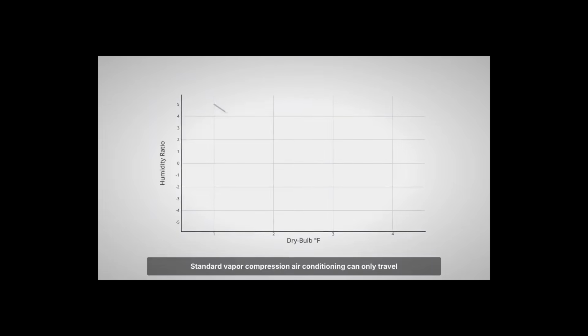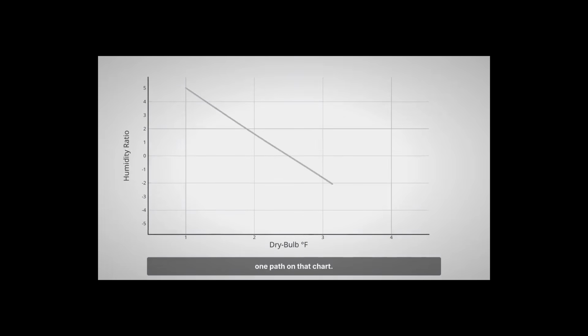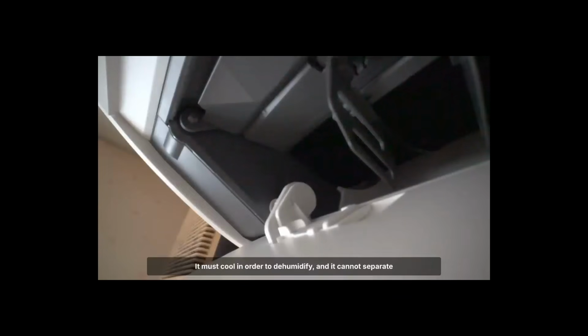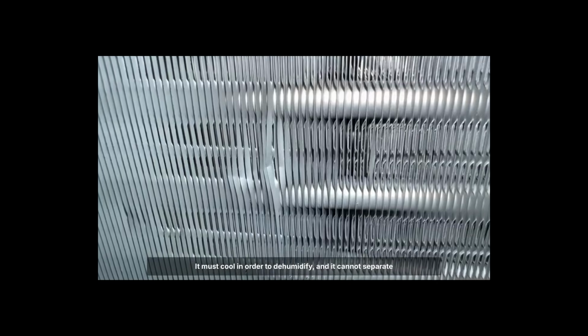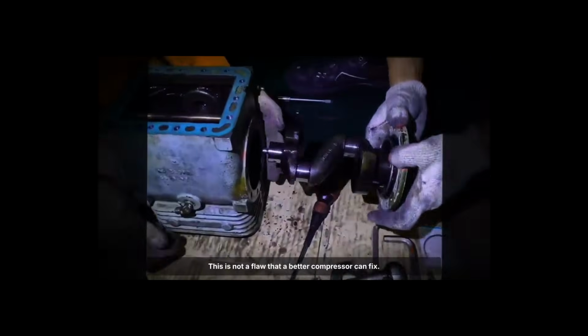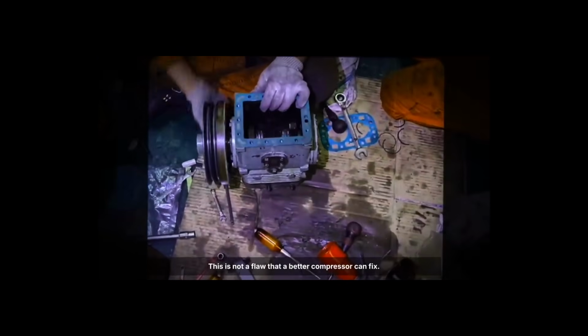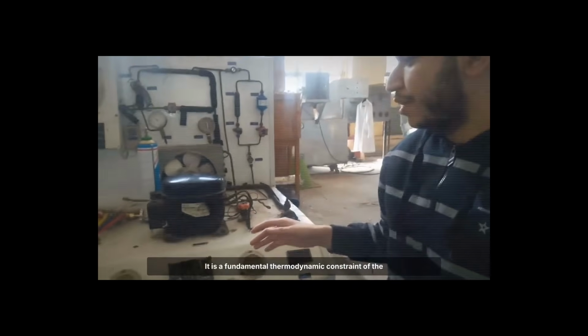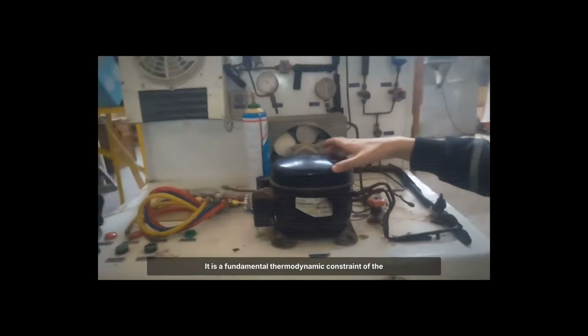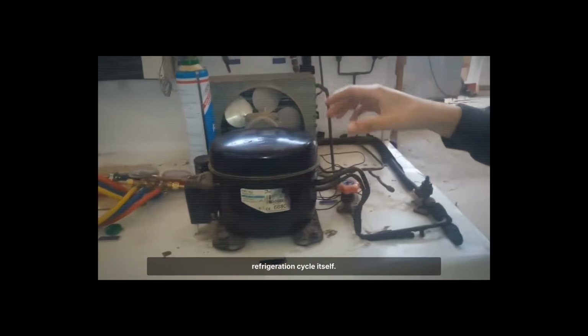Standard vapor compression air conditioning can only travel one path on that chart. It must cool in order to dehumidify, and it cannot separate the two tasks. This is not a flaw that a better compressor can fix. It is a fundamental thermodynamic constraint of the refrigeration cycle itself.